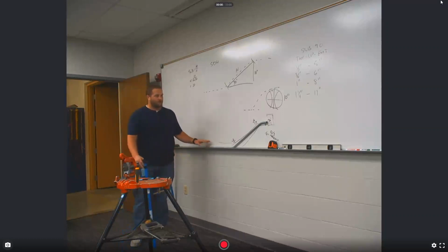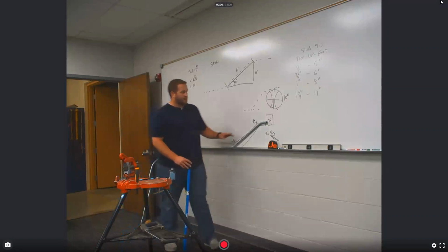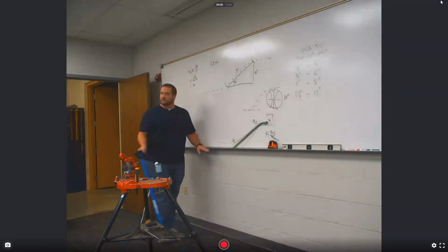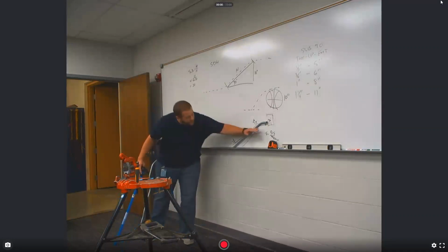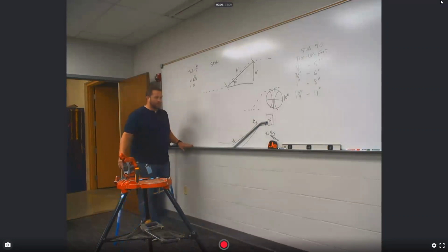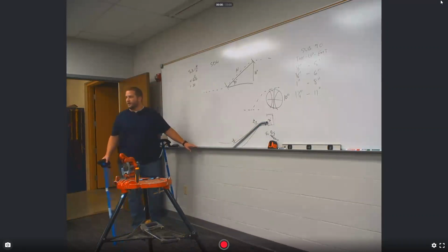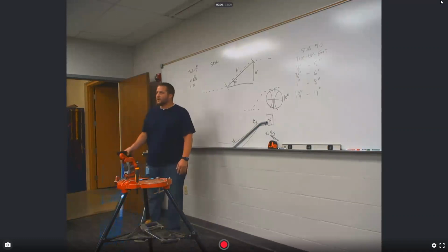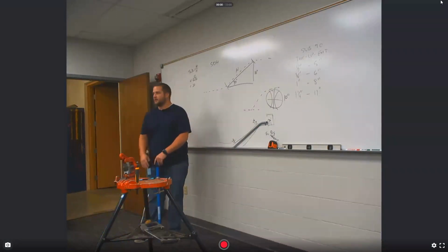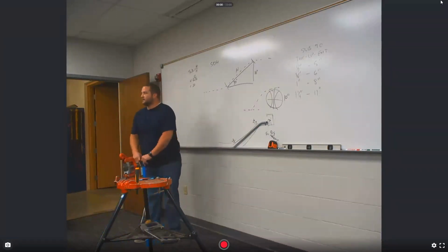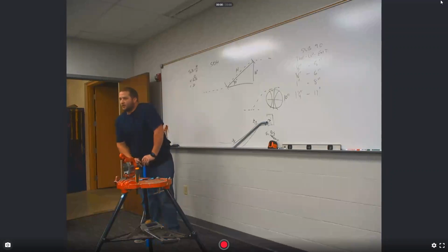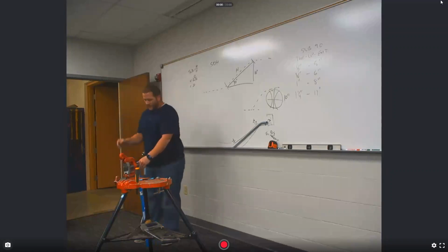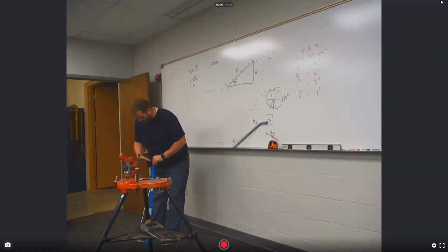But okay, so that's pretty close. And as long as it doesn't look bad, that's a little bit high. But if I put that in the coupling and then force feed it in my support, it's going to look pretty darn good, right? But our math was right. That's all I'm concerned about here. When you do your bends, it might have a dog in it. That stuff goes away with practice. But what I want to see is that your bend lines up with that 30-degree line.